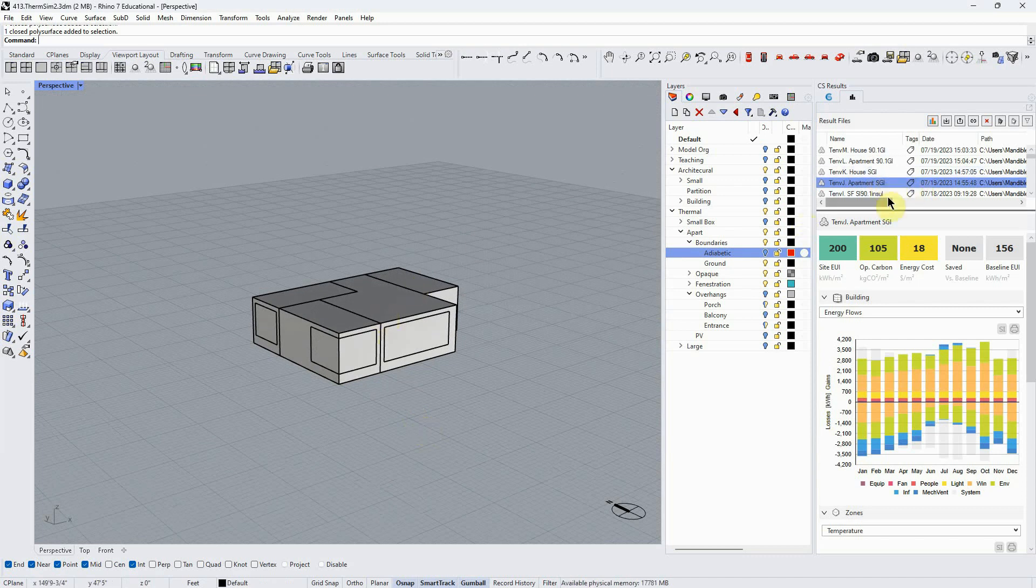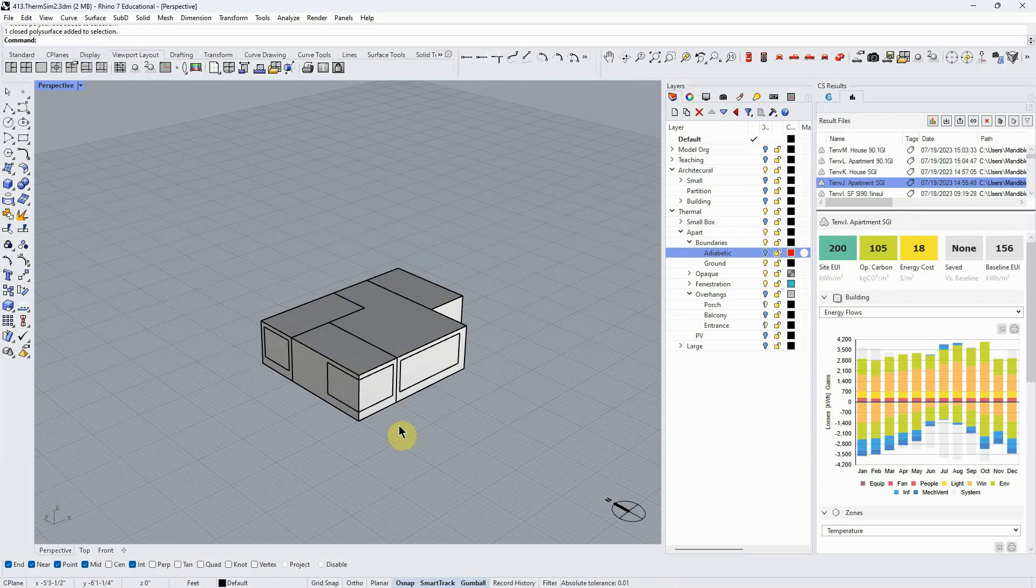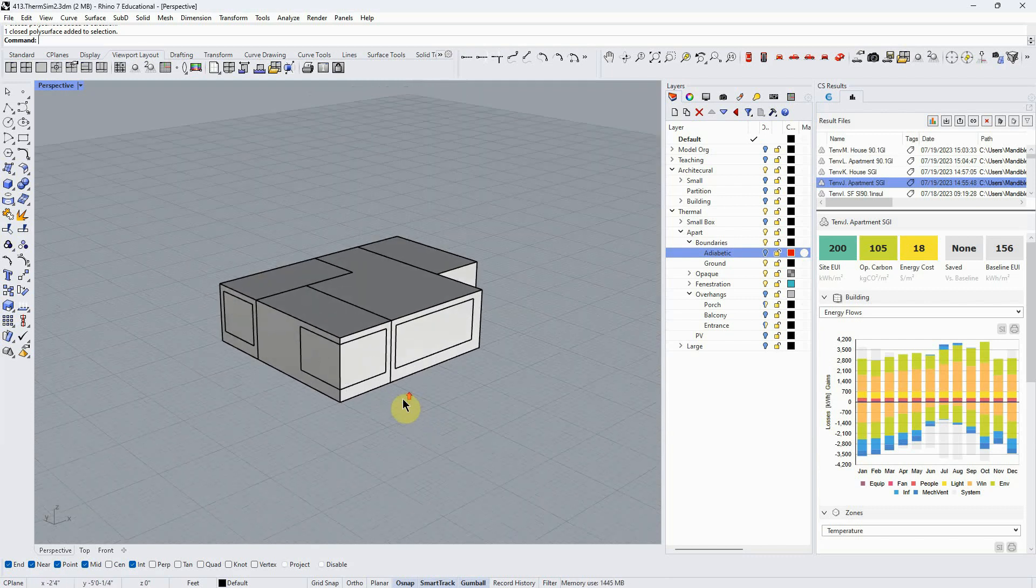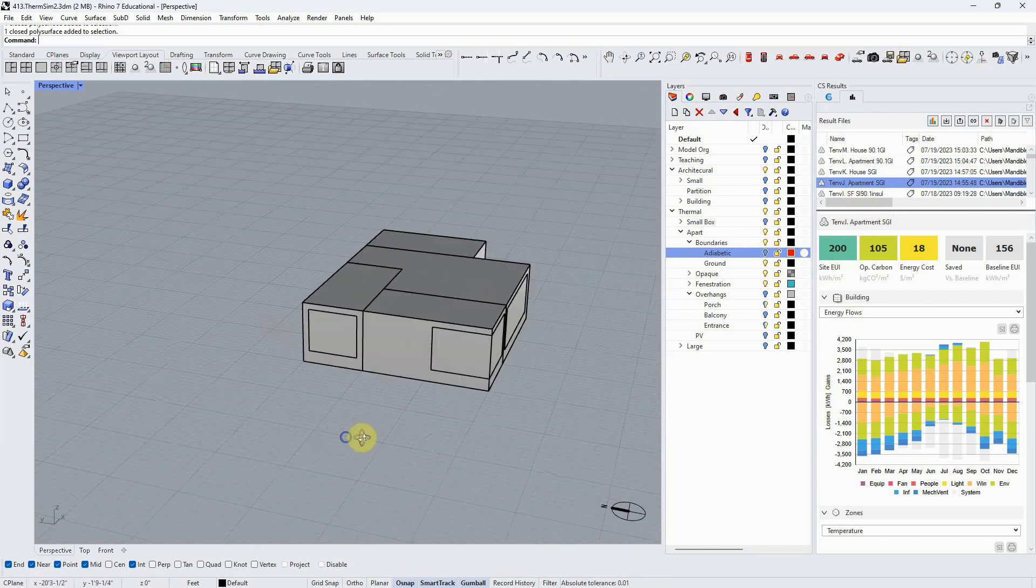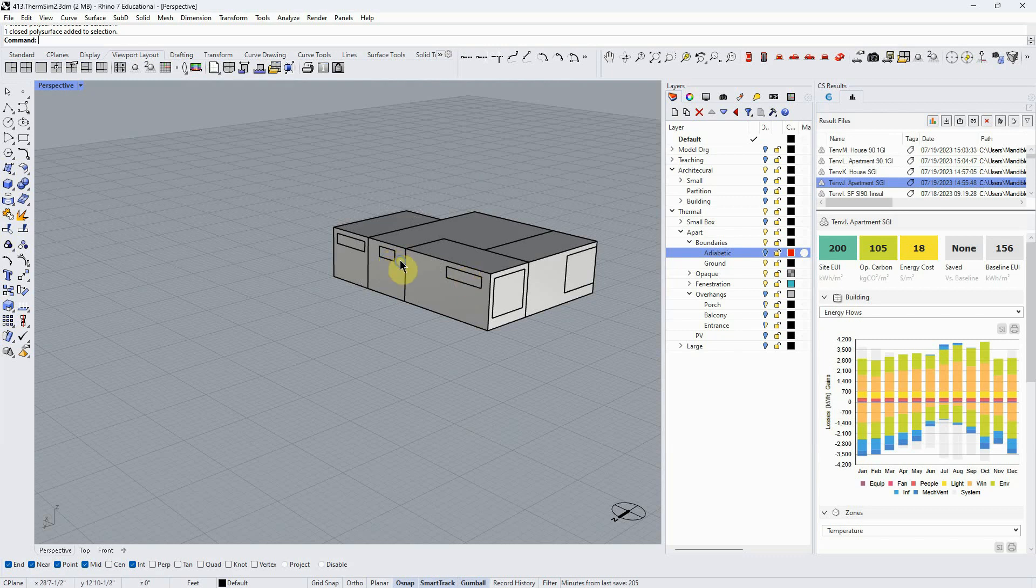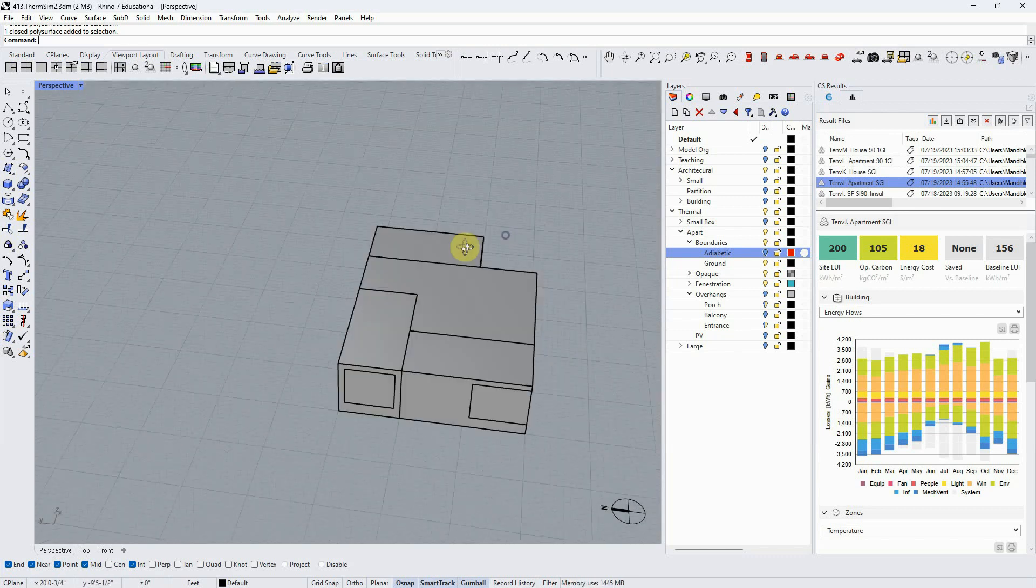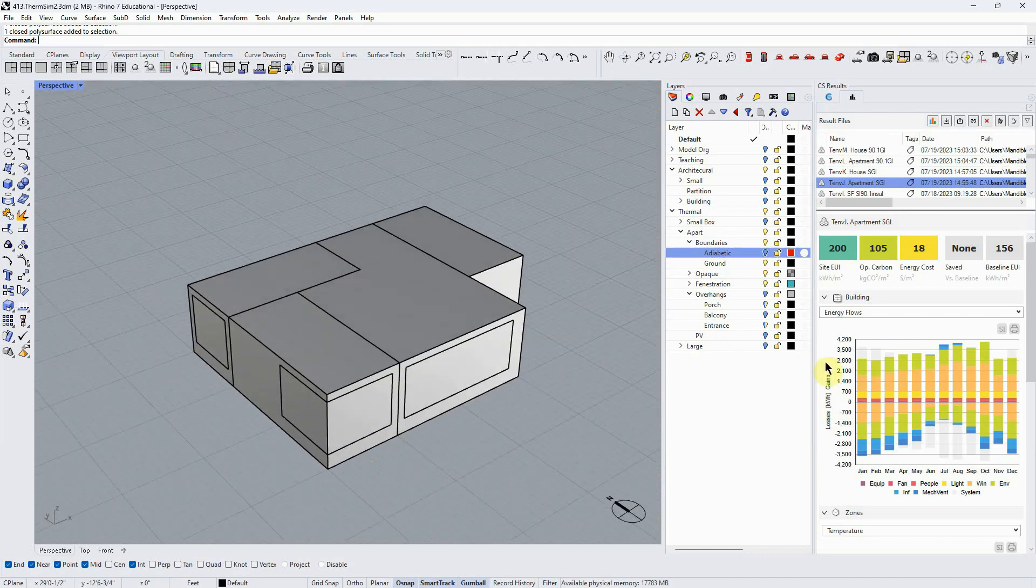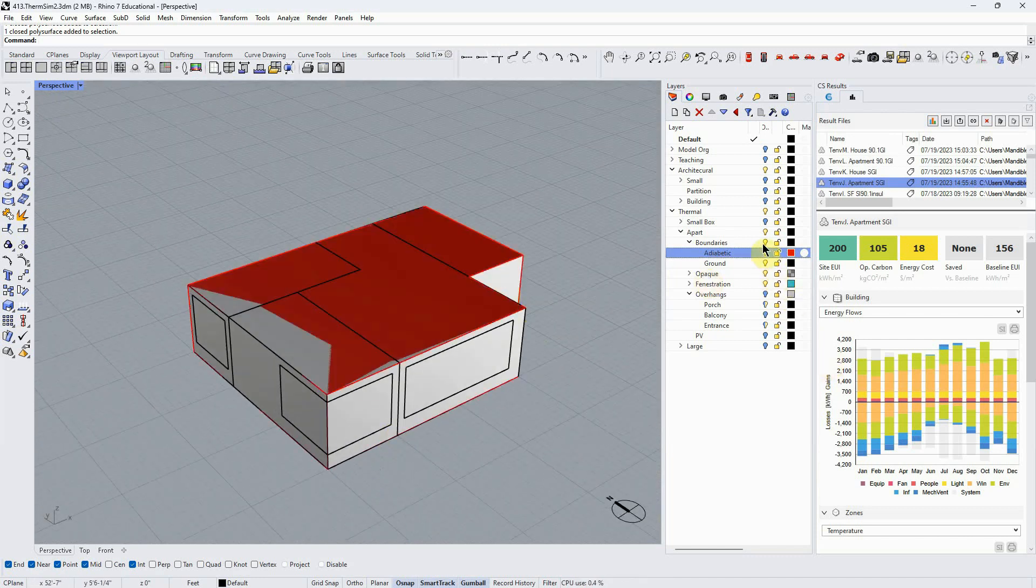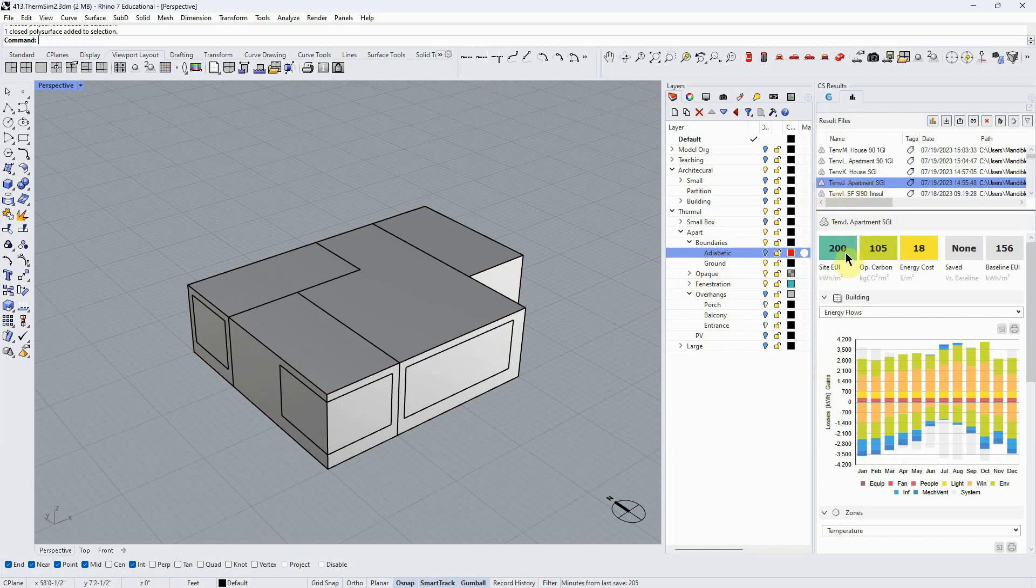Let's see what effect that has—spoiler alert, it was surprising to me. So I've run several iterations using exactly the same settings. It's just that multi-family—this is not accurate, but it's a comparison as we're learning. I say it's not accurate because the mechanical system probably in a building that was an apartment inside a larger building is going to be different than a single family house. But I'm talking about the physics of how this works and us learning how to experiment with this modeling workflow. If we start with the apartment, I ran a simulation, and by the way with the house too, I didn't have these windows in there—those are not part of the simulation, and I don't have the shading that I had in place. So it's exactly the same form, just one is sitting on the ground and the other is surrounded by the apartment. I ran the apartment first, and the EUI I got was 200.